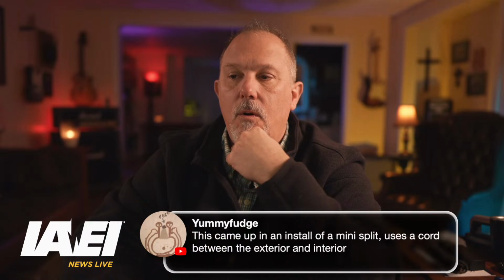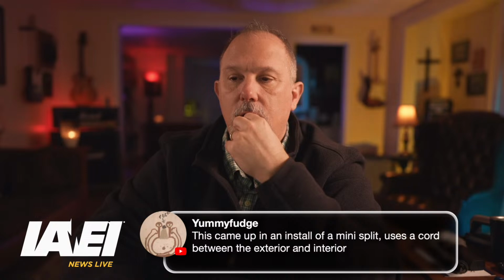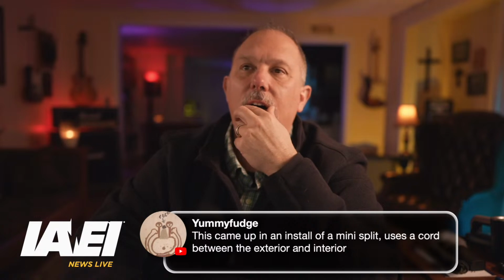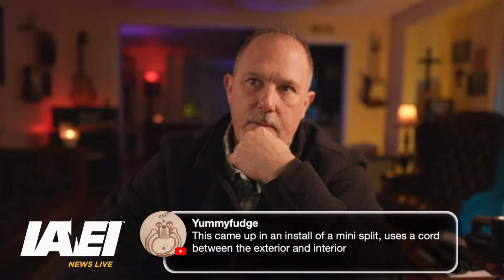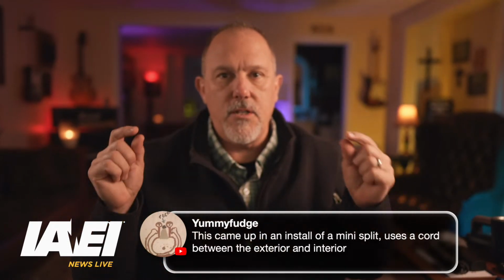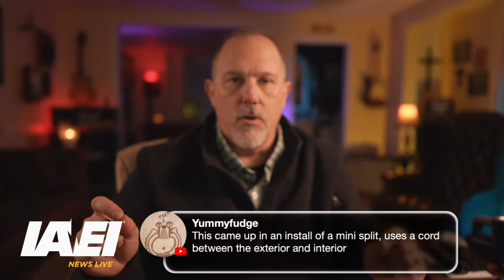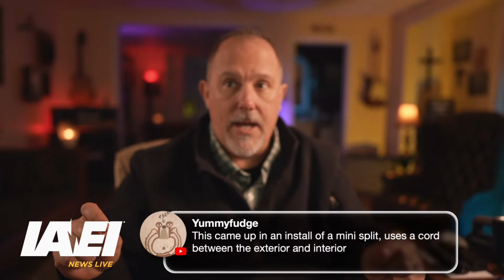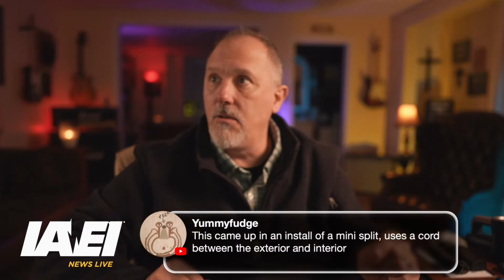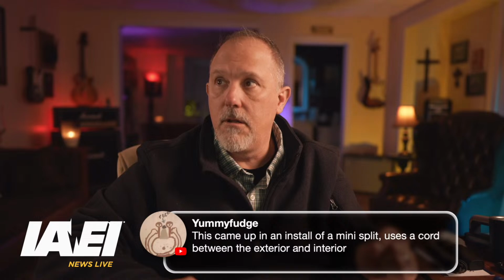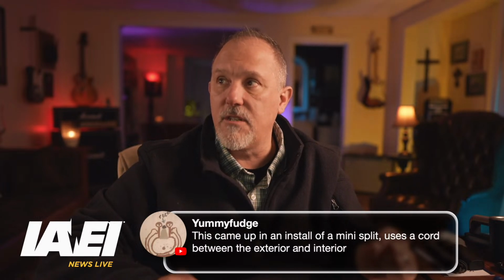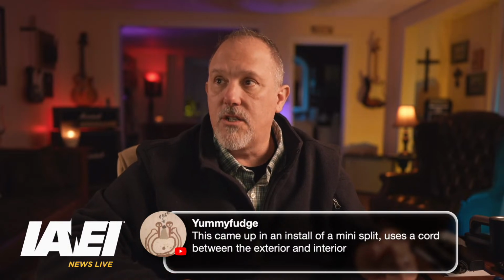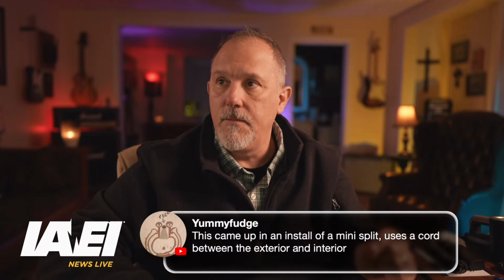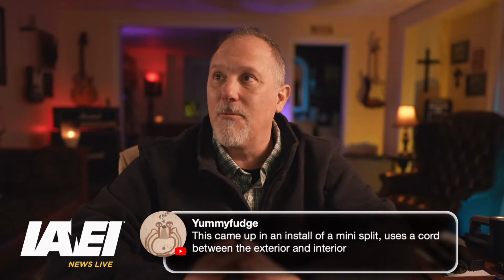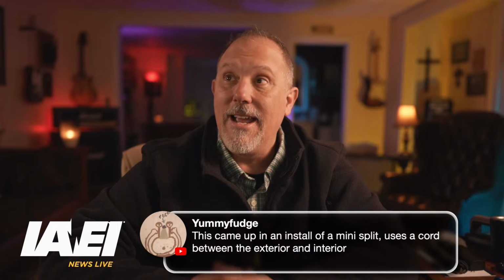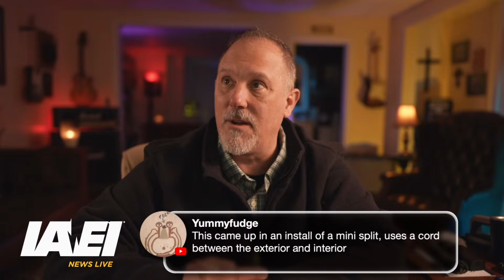Wow, Yummy Fudge. That's a good point. And if you call that conductor between the mini splits a flexible cord or flexible cable, then you're back to 400.12, saying what can't you do with it. Uses not permitted: where concealed by walls, floors, or ceilings; located above suspended or dropped ceilings; installed in raceways except as permitted in the code; it has to be protected from physical damage; it can't run through a doorway, window, or similar opening; and it can't run through holes in walls, structural ceilings, suspended ceilings, drop ceilings, or floors.